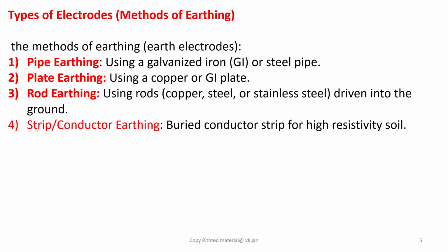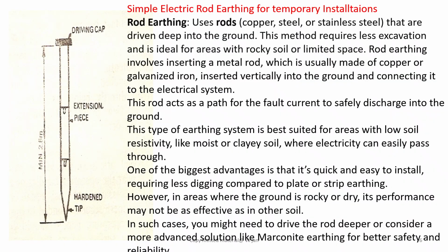Say most of the government code recognizes following type of electrodes. That means methods of earthing: pipe earthing, plate earthing, rod earthing, strip and conductor earthing, apart from chemical earthing. Simple electrical earthing for temporary installations. Friends, rod earthing uses rods that may be of copper, steel, or stainless steel. These are driven deep into the ground. This method requires less excavation and is ideal for areas with rocky soil or limited space.